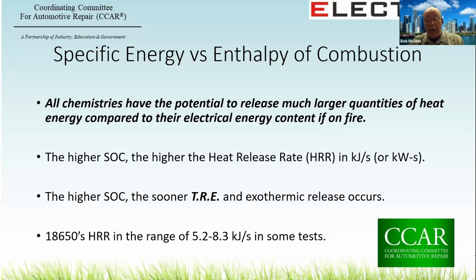So if you grasp nothing else from this presentation, it's this: all chemistries of lithium have the potential to release much larger quantities of heat energy compared to the electrical energy that they can store, if that battery is on fire. The higher the state of charge, the higher the heat release rate. And in some tests, the 18650 heat release range is in the area of 5.2 to 8.3 kilojoules, which is significant for one little battery.